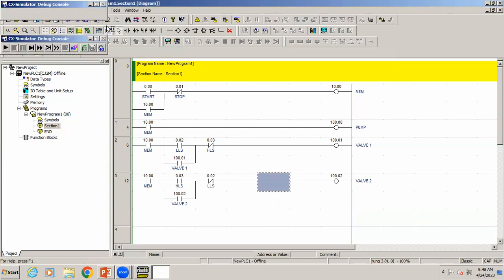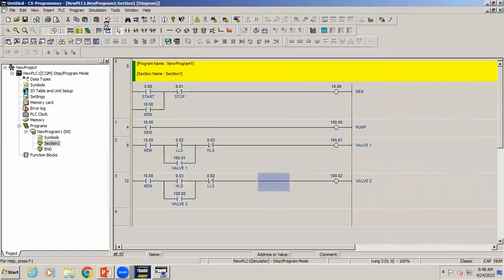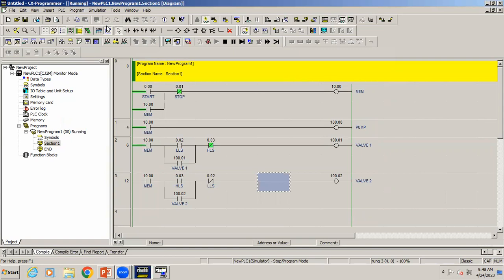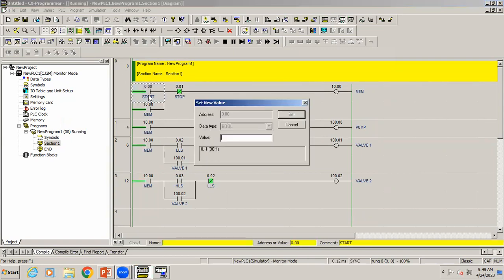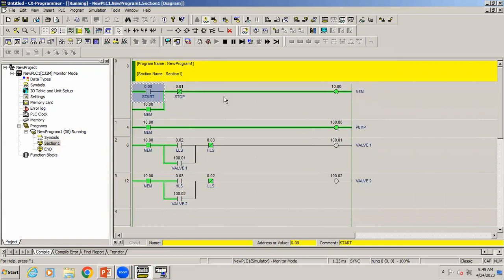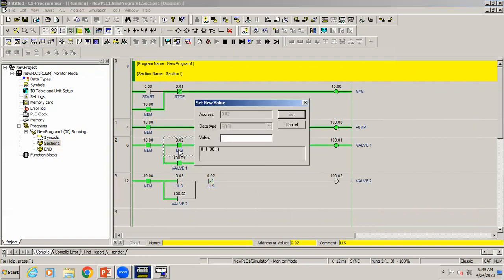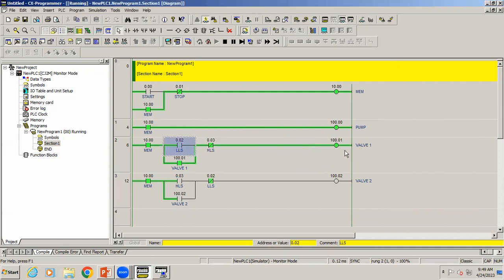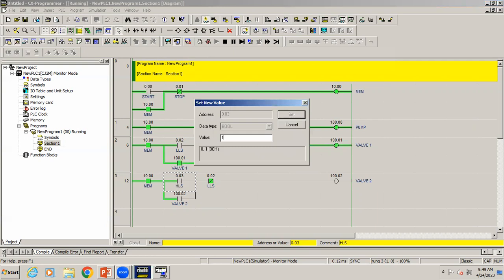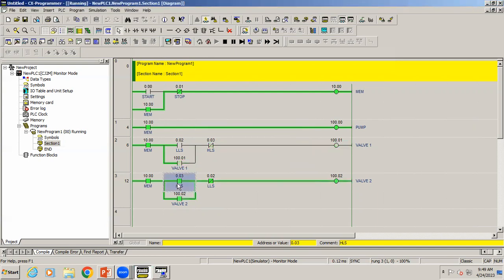Now we can check it. When I press the start push button, the pump turns ON. After releasing the start push button it remains ON due to latching. The tank level is increasing. Since the tank is empty, the low level sensor is in the ON state, so valve one opens. Once the tank level rises above the low level sensor, the sensor turns OFF, but the valve remains in open state due to latching. The level keeps increasing. Once it reaches the high level sensor, valve one closes and valve two opens.